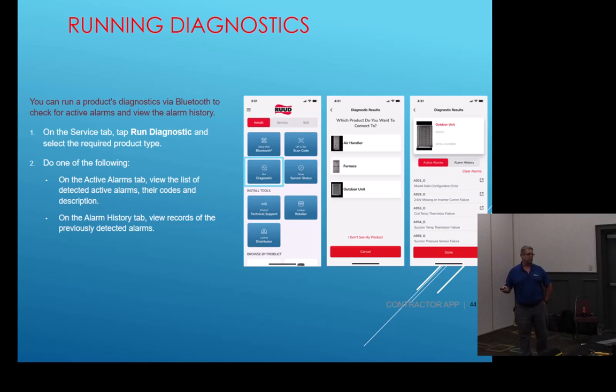Diagnostics. We're going to talk about diagnostics quite a few times during today here, okay? But if we have the guest feature, we're going to click on diagnostics, choose our outdoor equipment they've chosen here, and it'll tell you all of the alarms that we have on our outdoor equipment. Here's an A001 model data configuration area, 240 volts inverter comm failure, coil thermistor failure, suction temperature thermistor failure, suction pressure sensor failure. Okay? One of the things I want to point out, guys, and if you call me and you say, hey, I have a 953 coil thermistor code. What number? What's the code? It's an A953. It's an A953 what? I need that other letter designation, and you want that also, because it's going to tell you the piece of equipment that you're working on.